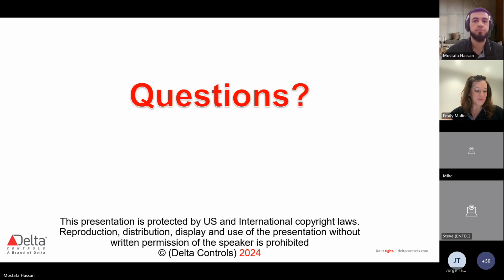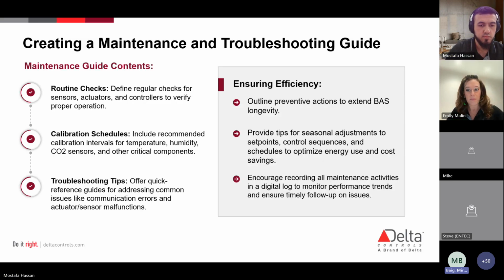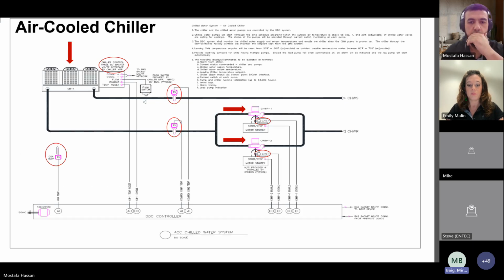Yes, hi, no problem. I have another question regarding the pumps slide. We were talking about the chilled water pumps being lead-lag, and these days we get pumps with smarts built in that are capable of having that lead-lag automatic switchover. Typically what we'd want to see is the BAS having command of those pumps through physical hardwired start-stop, but what do you think about the smarts built into the pumps? Would that be useful just to use and monitor?